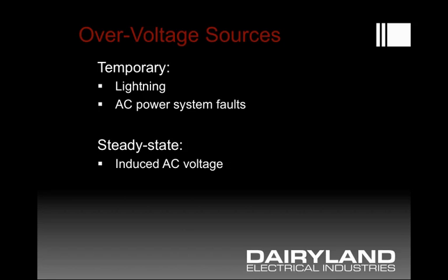There are a couple different sources of overvoltage. There are temporary conditions that exist only during an event such as a lightning event, or an AC power system fault from an AC distribution or transmission system that is there only for the duration of the fault until a clearing device operates, such as a power breaker. Or it could be that there are just steady state concerns, and those are induced AC voltage from overhead power lines. Where a pipeline runs in a common corridor with a power line, an induced voltage will appear on that pipe at various levels, and that voltage needs to be reduced for worker safety mainly, and that can be done on a steady state basis.